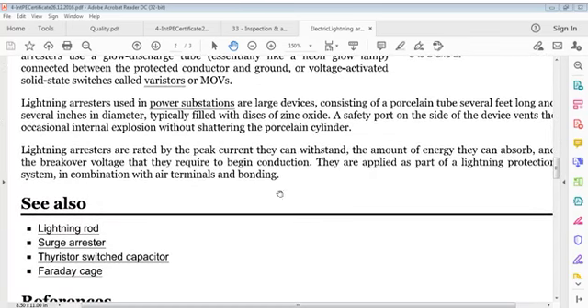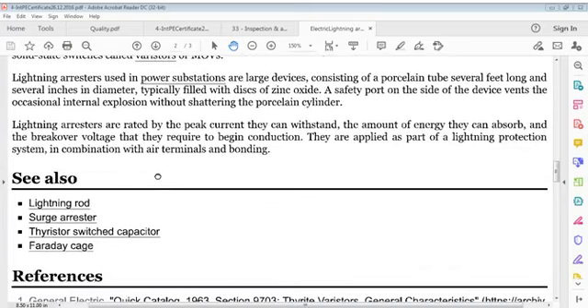Lightning arresters used in power substations are large devices consisting of a porcelain tube several feet long and several inches in diameter, typically filled with discs of zinc oxide. A safety port on the side of the device vents an occasional internal explosion without shattering the porcelain cylinder.